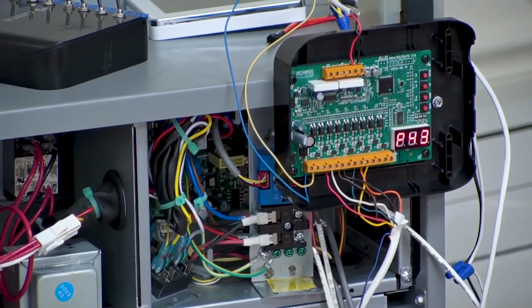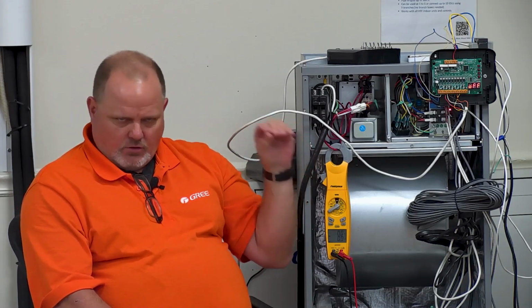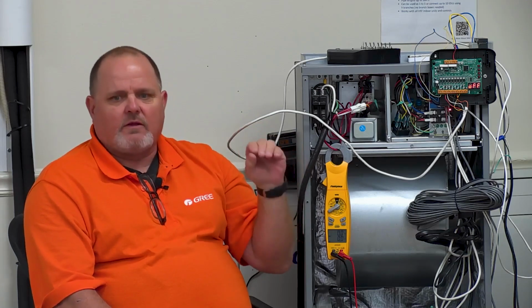If we've got a power problem or the machine, let's say, doesn't have enough refrigerant in it, but it's barely squeaking by, you're saying that that particular indoor unit has priority operation over any indoor unit attached to that same condenser. You're giving that indoor unit basically the ability to run even if the other ones can't. If we can't keep them all running, we're going to say that this is the one I do want to be able to work, if it will still work. So that's what priority operation means. You want that unit to be the priority, which makes sense.